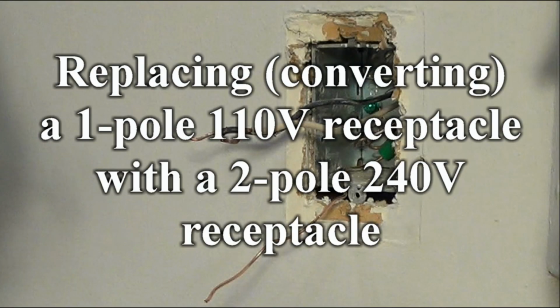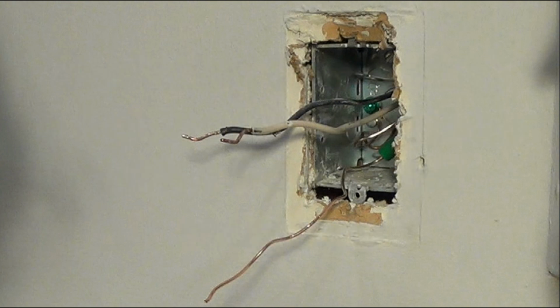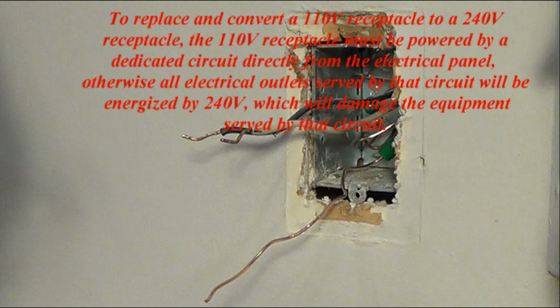Replacing, converting, a 1-pole 110 volts receptacle with a 2-pole 240 volts receptacle. To replace and convert a 110 volts receptacle to a 240 volts receptacle, the 110 volts receptacle must be powered by a dedicated circuit directly from the electrical panel.